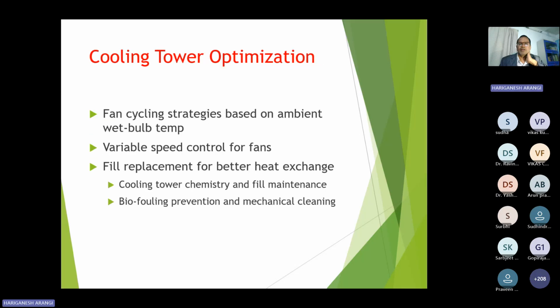Cooling tower optimization: a fan cycling strategy based on ambient wet bulb temperature, and we use variable speed control systems. In the cooling tower, the fills are better checked and replaced every 2, 3, or 5 years, because raw water is used in the fills. Sometimes there will be biofouling, coatings, or they come to a brittle condition, so regular cleaning and replacement is mandatory to improve the plant efficiency.